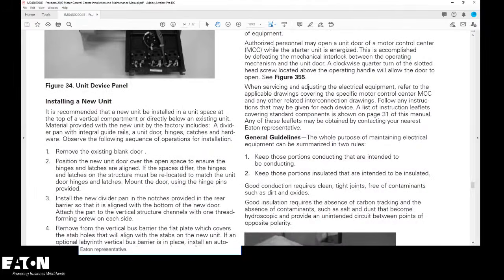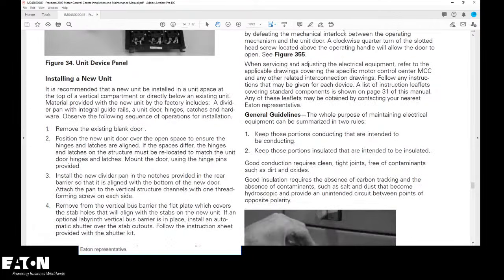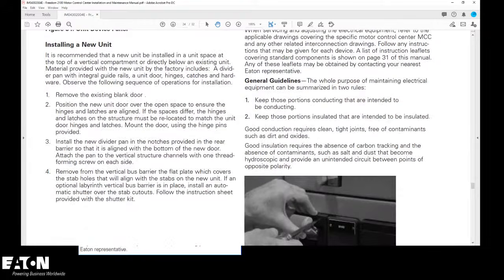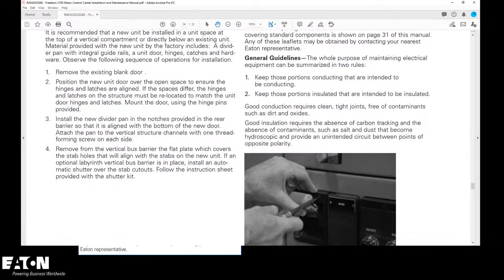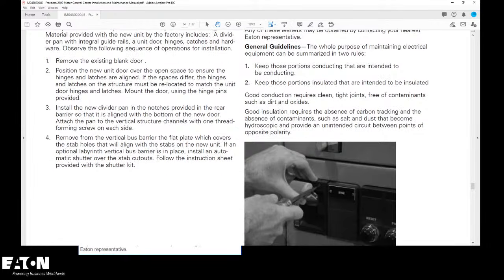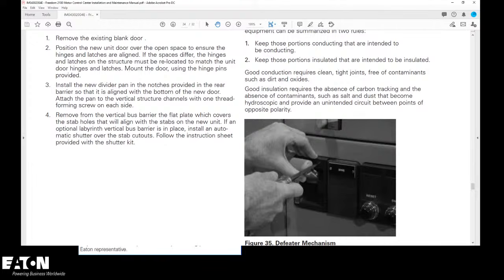When servicing and adjusting the electrical equipment, refer to the applicable drawings, list of instructions and leaflets. The whole purpose of maintaining electrical equipment can be summarized in 2 rules: keep those portions conducting that are intended to be conducting, and keep those portions insulated that are intended to be insulated. I like that. It really simplifies it, doesn't it? Good conduction means clean, tight joints, free of contaminants such as dirt and oxides. Good insulation requires absence of carbon tracking and absence of contaminants, salt, dust, etc.